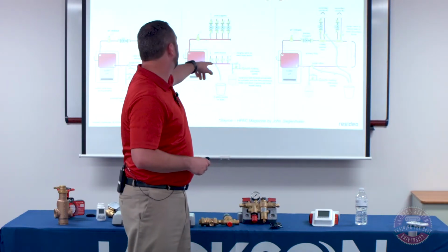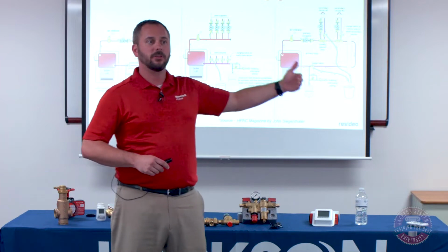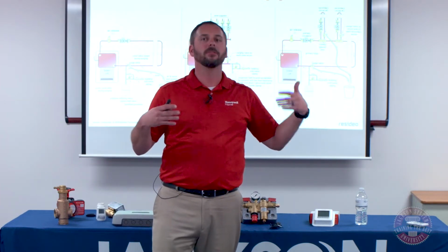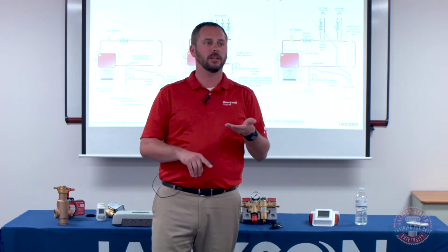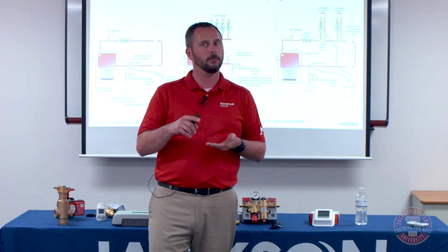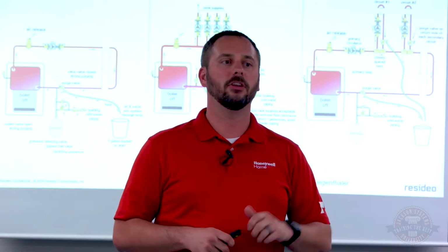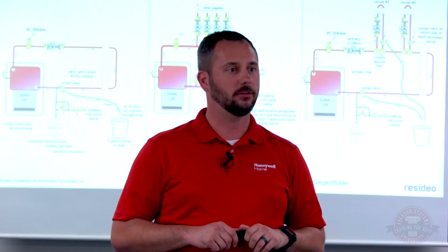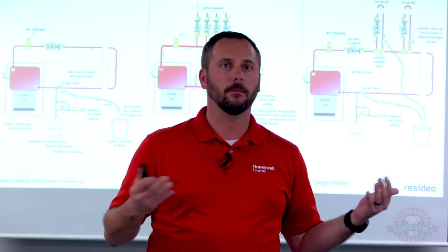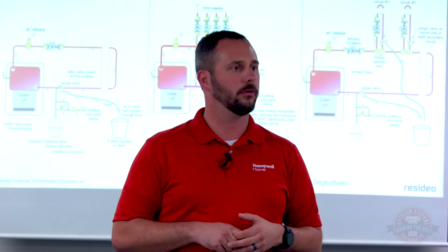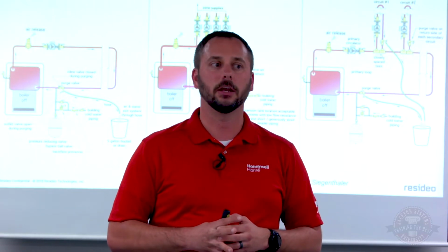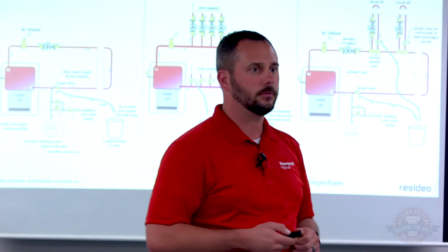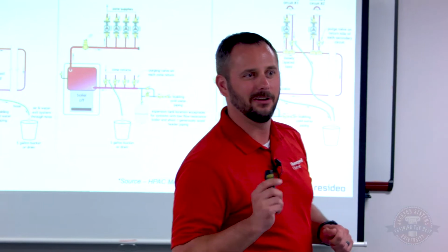Usually what you want to have is your water makeup coming in. There's different ways to do it, but typically it's teed into the line between the expansion tank and air eliminator, and then your pump is always on the discharge of that. You never want to pump into the expansion tank. But there's different placements. Sometimes mechanical rooms don't permit the perfect schematic that you see here. I'm not sure if that answered the question or not. I think so.